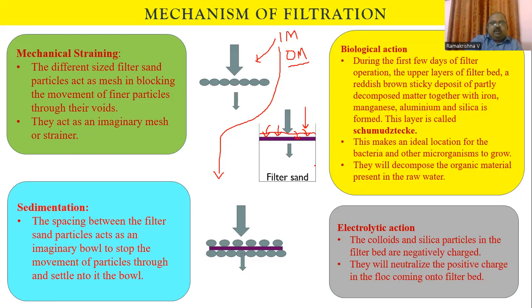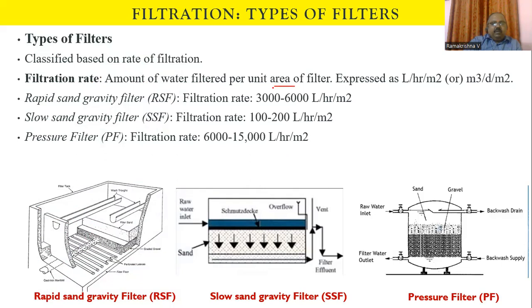There are three types of filters based on the rate of filtration. Filtration rate is defined as the amount of water filtered per unit area — how much water in liters per hour passes through one square meter of filter surface area. The major filters used are: rapid sand gravity filter, slow sand gravity filter — mainly employed in community water treatment systems — and the pressure filter, used at isolated locations for specific purposes.